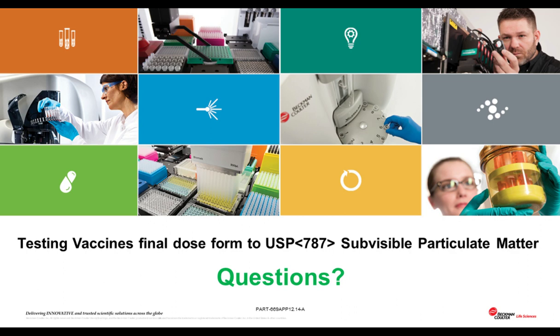Please explain again what equivalent spherical diameter means. Yes, certainly, that's a difficult one, but it's very important really, and it's why obscuration is used. So the particle counter is calibrated using certified calibration beads, which are of course spherical, but they're of a known size, and they obscure a fixed amount of light in the measurement cell. Now, subsequently, any particle that enters the measurement cell, doesn't matter what shape they are, if they obscure the same amount of light as the calibration beads, they can be said to have an equivalent spherical diameter.